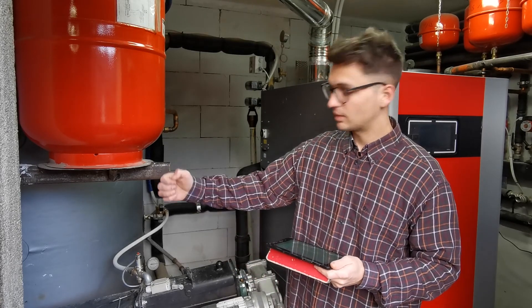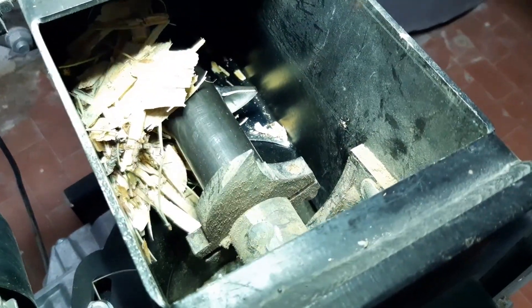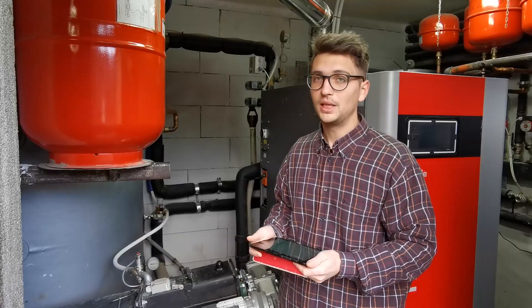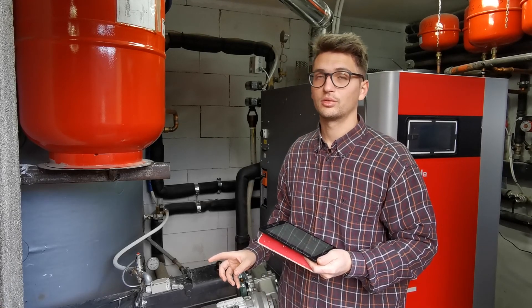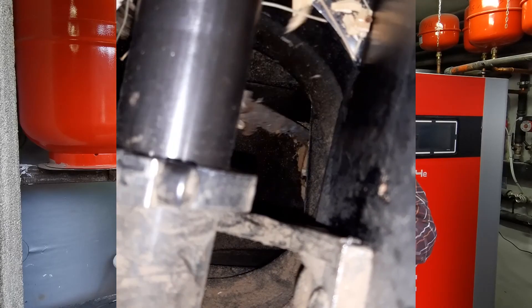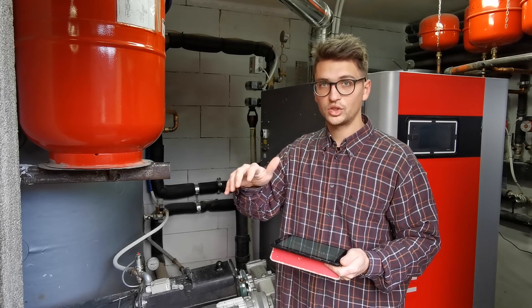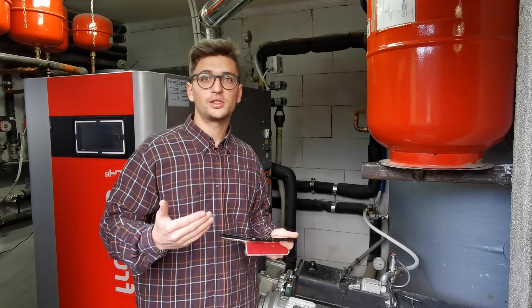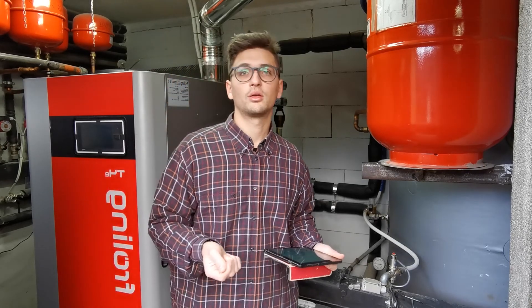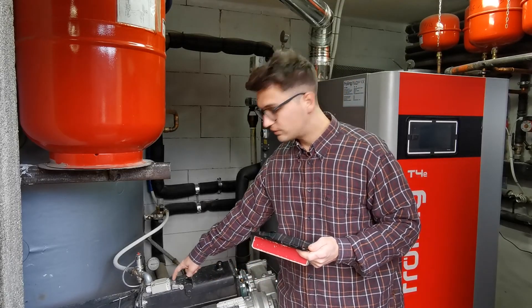During operation, you can see the wood chip coming from the main feeding screw. It falls down into one bin of the valve, the valve rotates, and the wood chip falls into the secondary screw. There are blades on top of the cylinder — this is necessary because long branches or long pieces of wood may block the whole system, so these blades cut them to let them pass. There are also torque controls: if the PLC sees too much current absorbed over a few cycles, it raises an alarm and stops the boiler — meaning something cannot be cut. This happened a few days ago with a long piece of iron. There is also a safety switch on the lid: if wood chip is blocked inside the stoker and tries to come out, the switch moves to the alarm position and blocks the stoker, requiring the operator to manually remove the material.